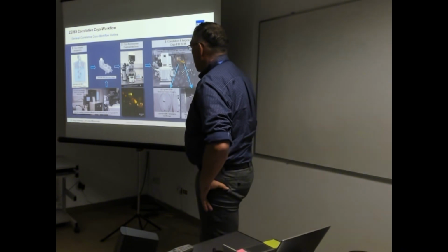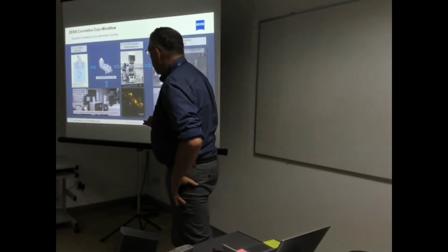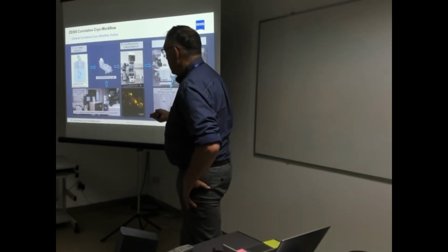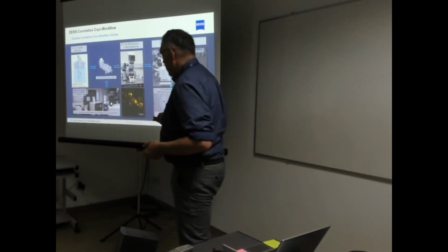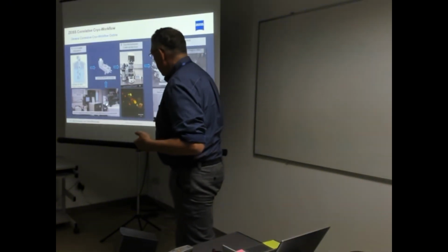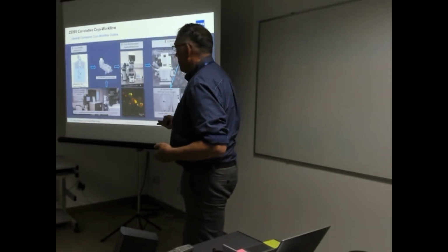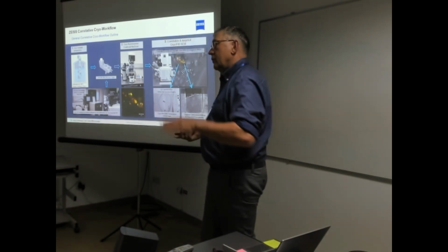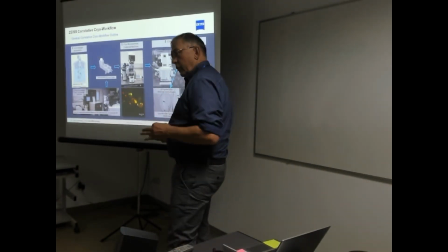What we can do is we can have this device which is called the high pressure freezer connected to a light microscope. We have the sample here above a light microscope in a little dish where the sample is still alive under room temperature conditions, and we can image this sample, select a certain time point we're interested in, and then click a button and pull this sample here above the objective lens into the high pressure freezer. This process takes about 1.5 seconds. So 1.5 seconds after we've seen the event, we have the sample frozen in ice.